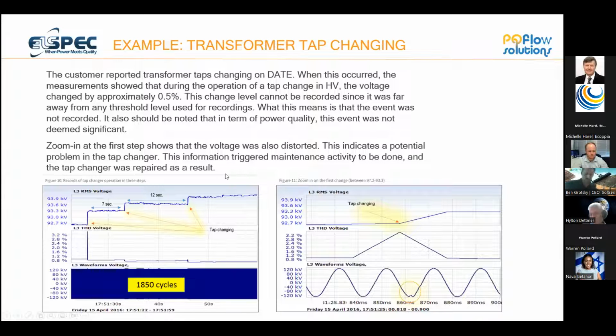We've got a whole lot of these meters in the city power network - probably about 600 of them - deployed over the last 5 or 6 years. When we put them in on the 275 kV network, we could see that the tap changes had a transient condition affecting the network, so anything hooked up onto that same network was seeing that transient. They were able to look at the tap changes, do maintenance proactively instead of reactively, and solve the problem from a risk perspective. So it all comes down to risk.